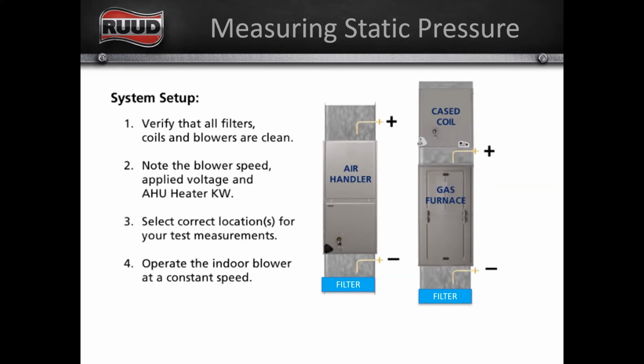Now, it's different with the air handler, because the indoor coil is part of that air handler. With a furnace and a cased coil, we don't know what coil is going to be used in that application with that furnace. So we don't calculate the pressure drop of the cased coil in with the furnace blower data. We do that with the air handler because we know what coil is in it.